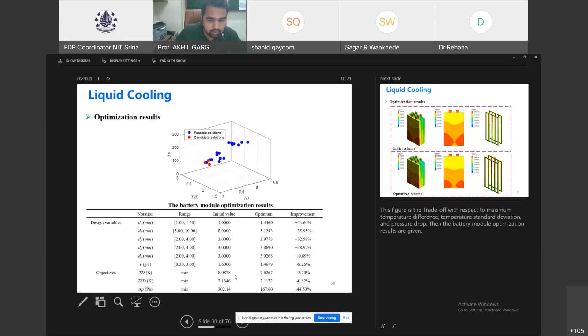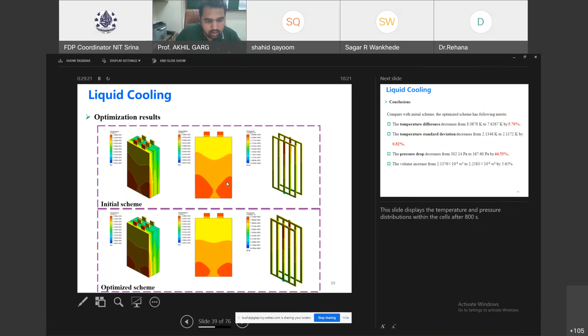Now we conduct the CFD again using the initial and optimized values. In the optimized scheme, we see much less heating, but in the initial scheme, when we input those results, we see much higher temperature. So we are able to reduce the temperature difference by 5%, the temperature standard deviation by 0.8%, and the pressure drop by 44%.